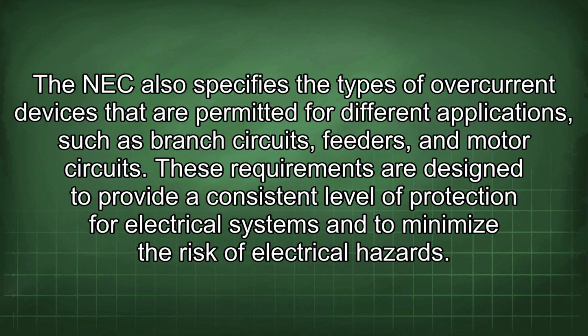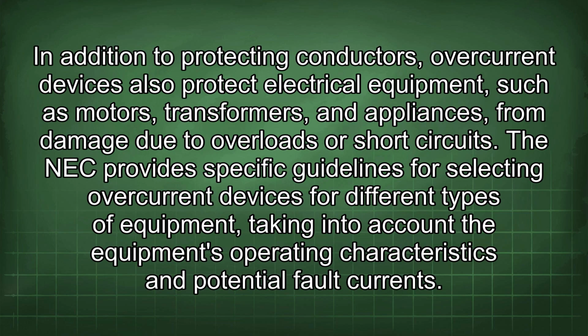The NEC also specifies the types of overcurrent devices that are permitted for different applications, such as branch circuits, feeders, and motor circuits. These requirements are designed to provide a consistent level of protection for electrical systems and to minimize the risk of electrical hazards. In addition to protecting conductors, overcurrent devices also protect electrical equipment such as motors, transformers, and appliances from damage due to overloads or short circuits.